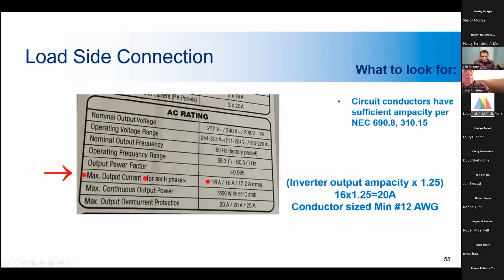All right. So when we're looking at the load side connection, you need to look at your circuit ampacity right here, max output current. And this is located on the inverter nameplate that lets you know what the output current is for that inverter. You want to size the breaker and the wire to handle 125% of the rated output ampacity of the circuit. And this is crucial for sizing conductors and to ensure the bus used at the interconnect is not undersized.